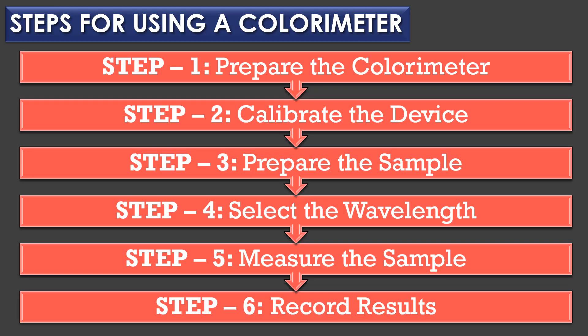Steps for using a colorimeter — there are six steps. Step one: prepare the colorimeter by turning on the device and allowing it to warm up. Step two: calibrate the device using a blank solution, either distilled water or solvent, to set the baseline or zero absorbance. Step three: prepare the sample by filling the cuvette with the sample solution. Step four: select the wavelength by choosing the appropriate filter to ensure the color of the solution is complementary to the wavelength selector. Step five: measure the sample by inserting the cuvette into the colorimeter; the instrument will measure absorbance or transmittance. Step six: record results — the colorimeter will display the absorbance or concentration value; record that result.